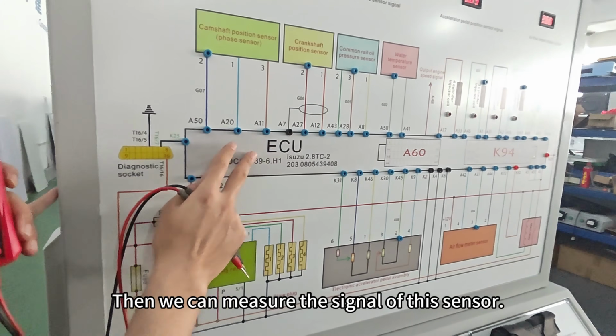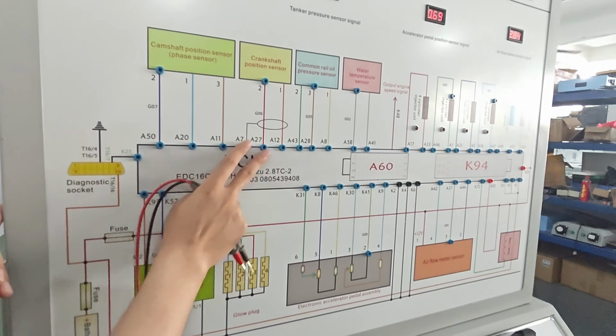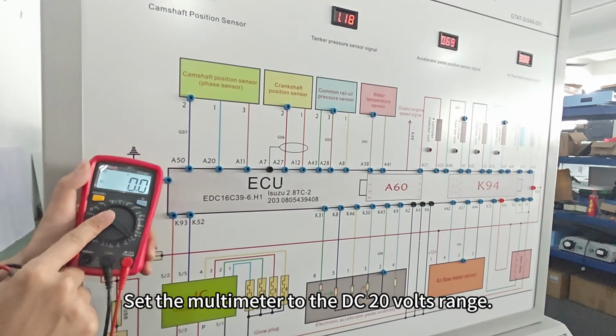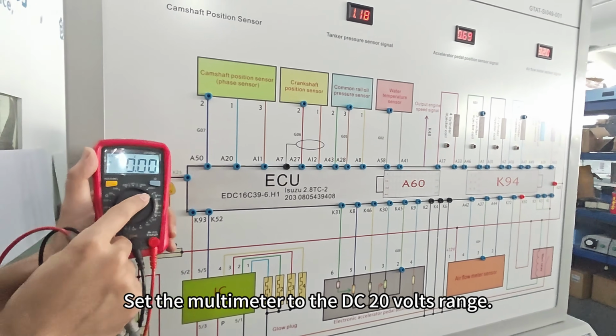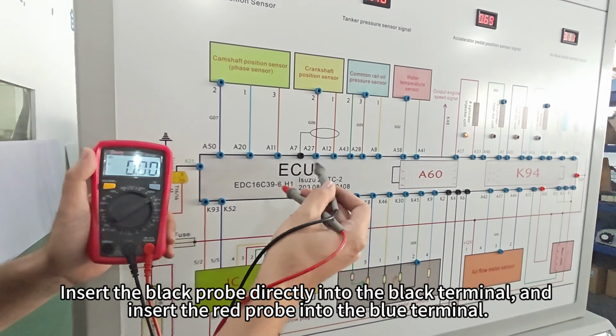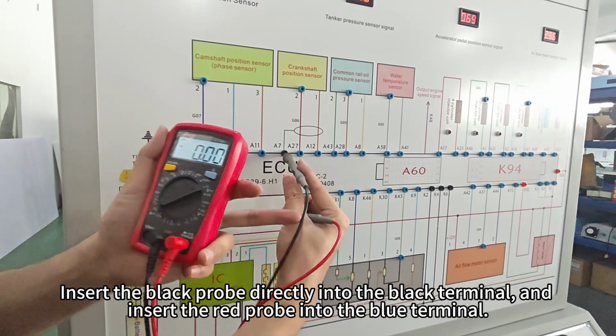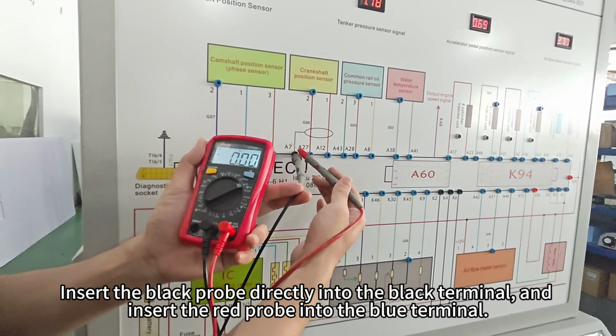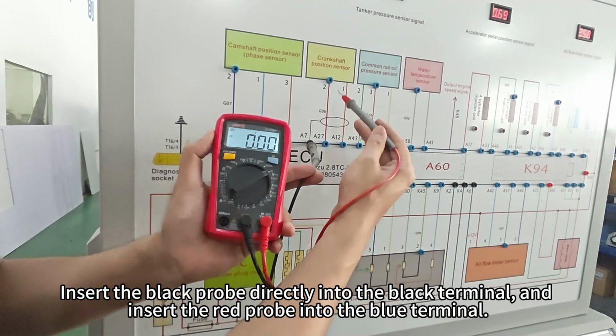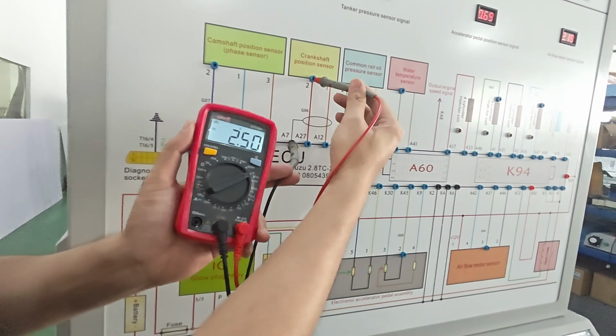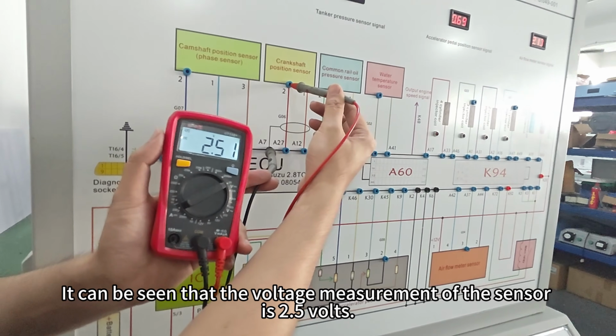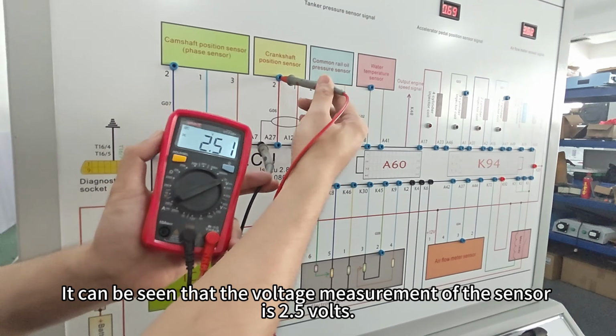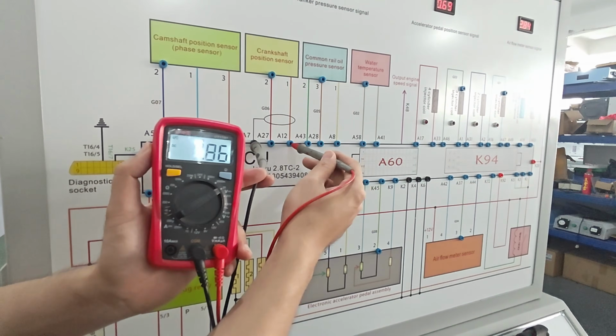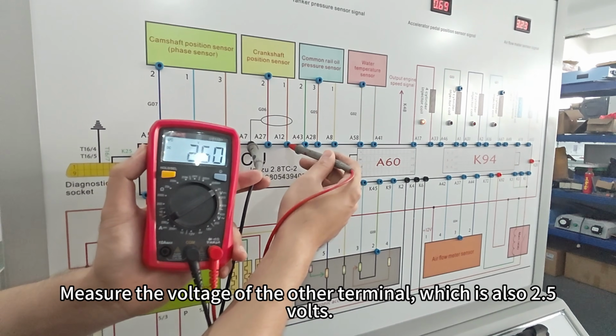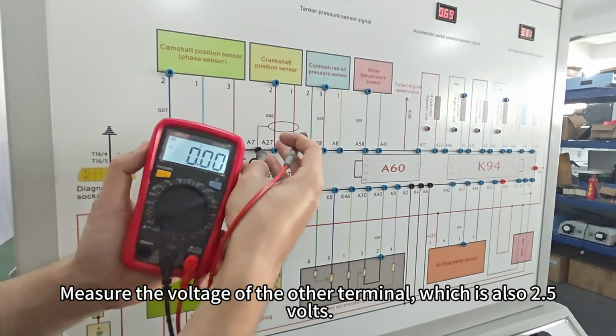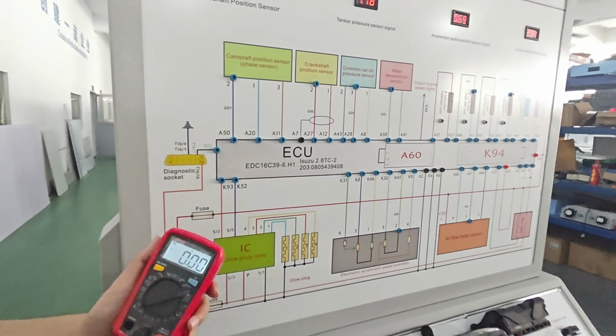Then we can measure the signal of this sensor. Set the multimeter to the DC 20 volts range. Insert the black probe directly into the black terminal and insert the red probe into the blue terminal. It can be seen that the voltage measurement of the sensor is 2.5 volts. Measure the voltage of the other terminal, which is also 2.5 volts.